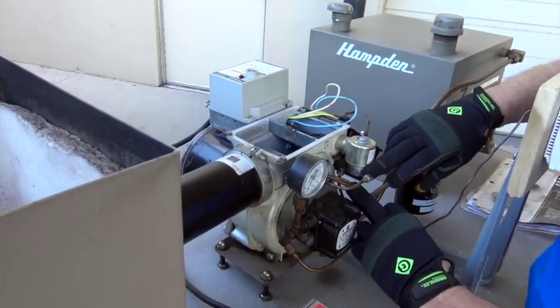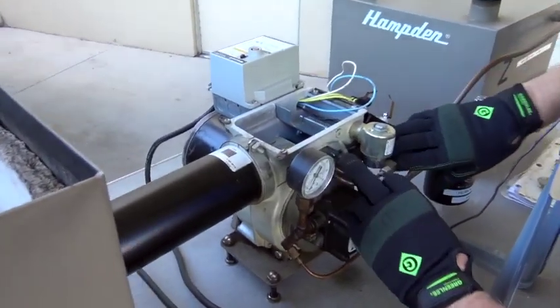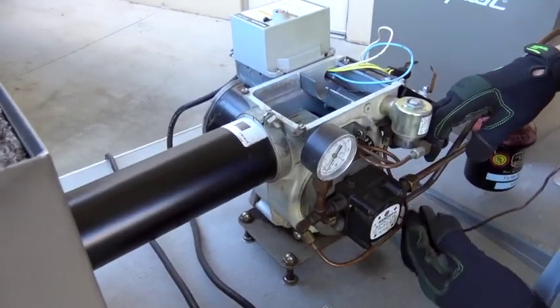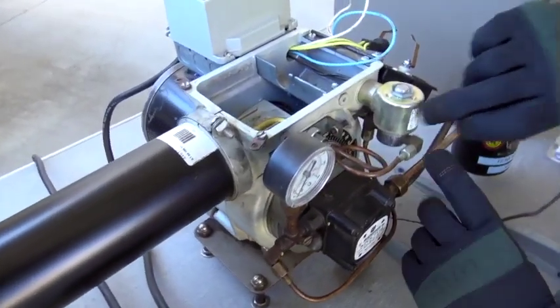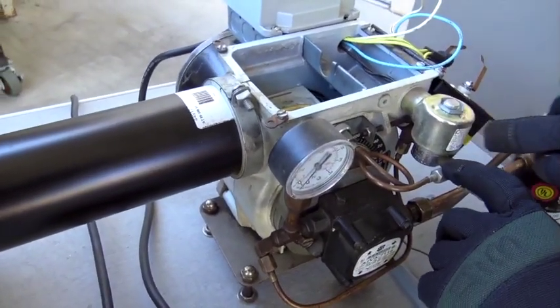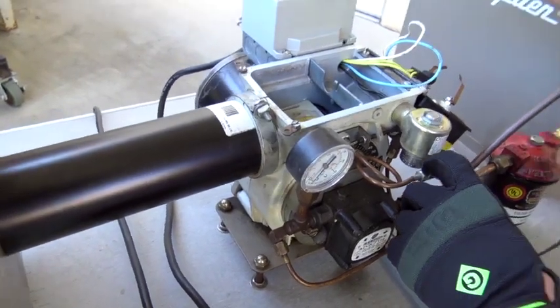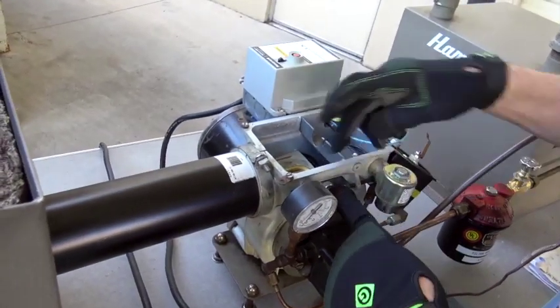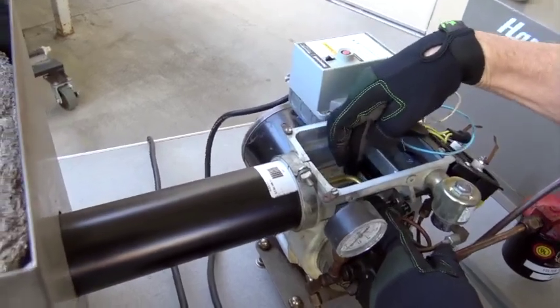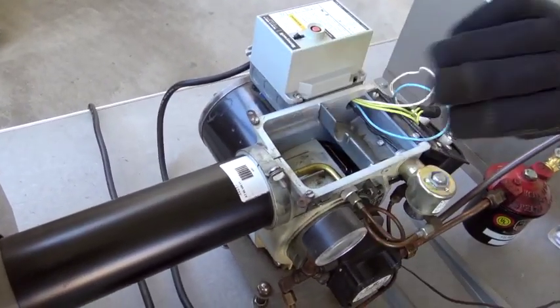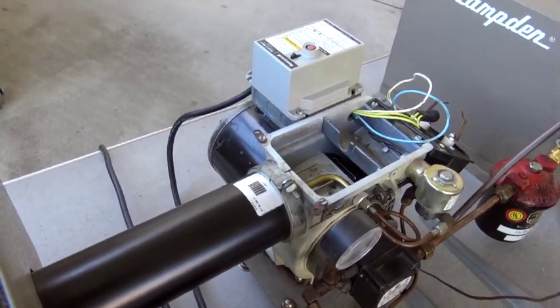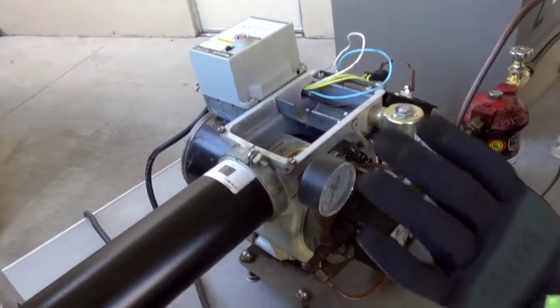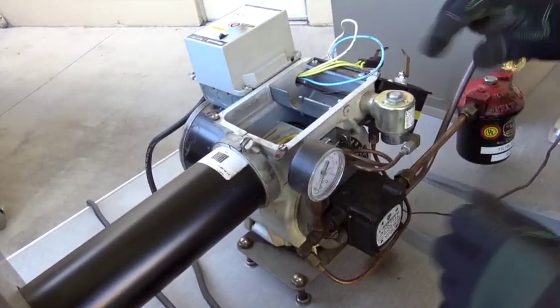It's going to pump through here, and it's going to go through the solenoid valve right here. See where the line comes? The solenoid is going to get energized on a call for heat through our primary control. And it's going to go through this fuel tube all the way to the nozzle. Now, this is the operation part of it.